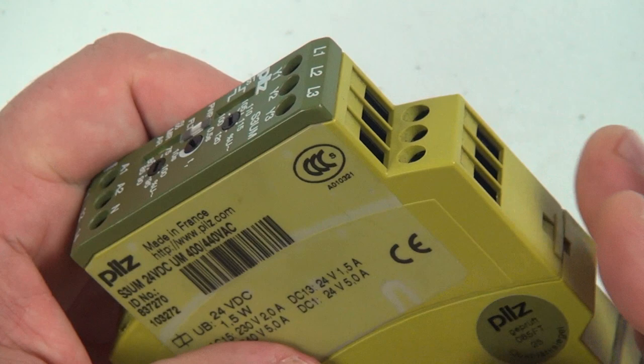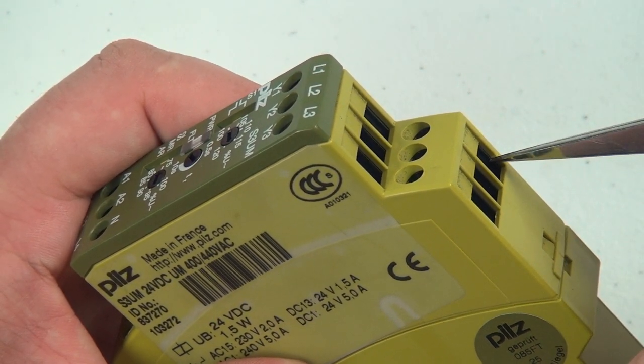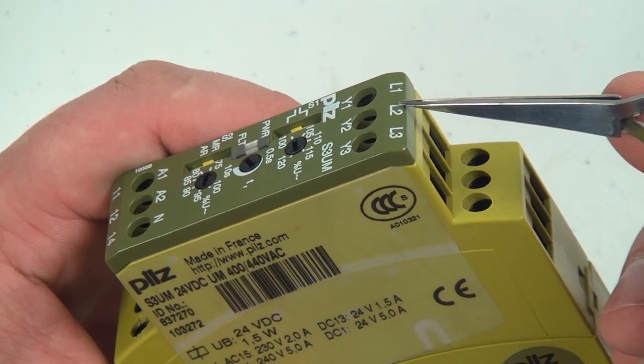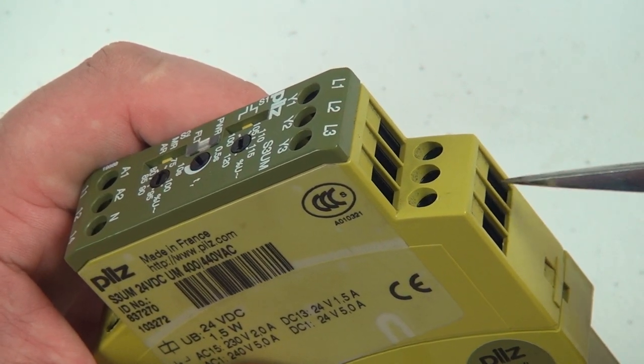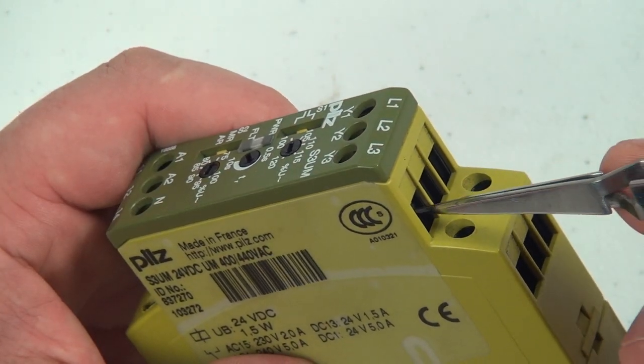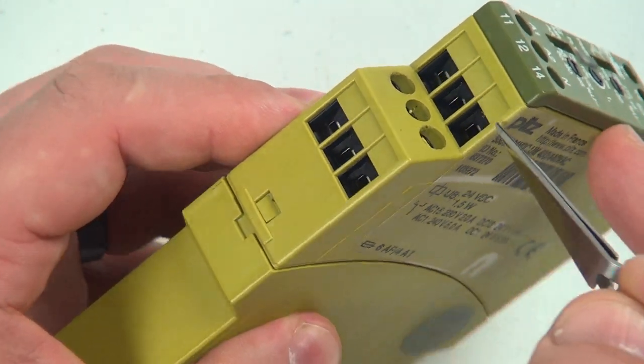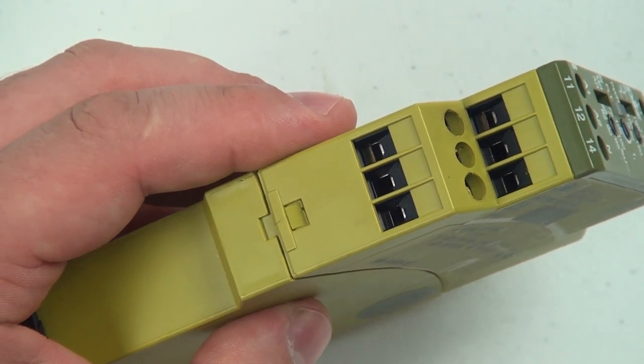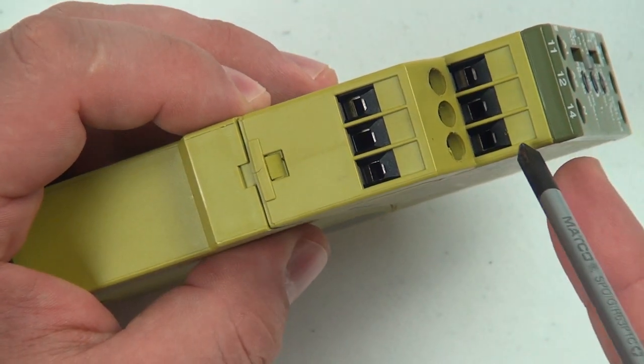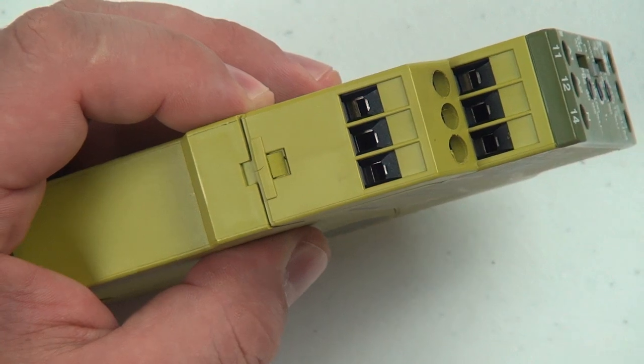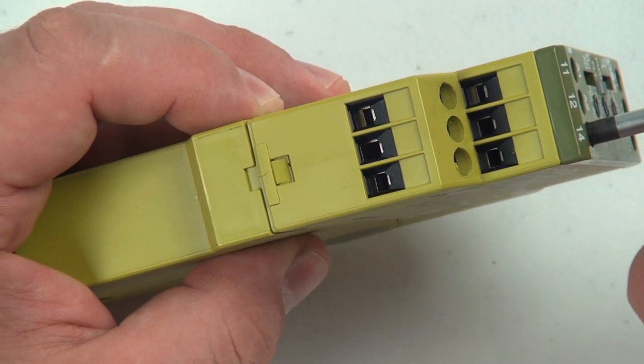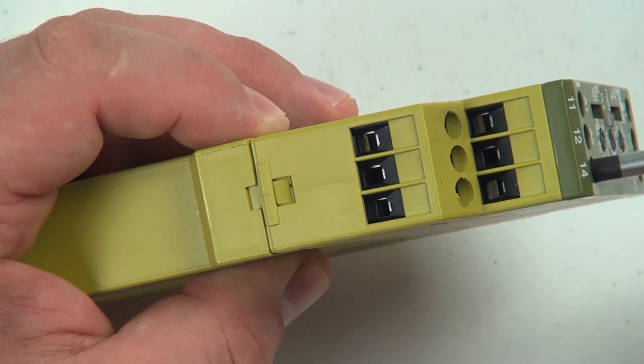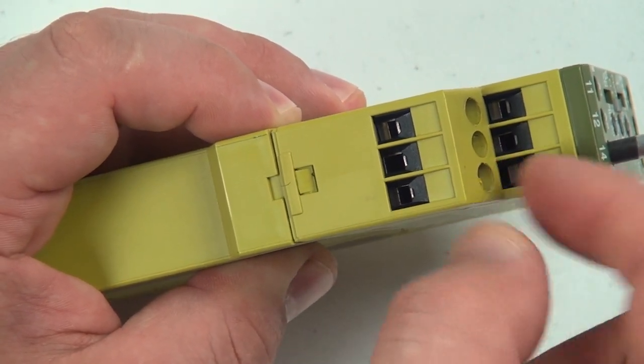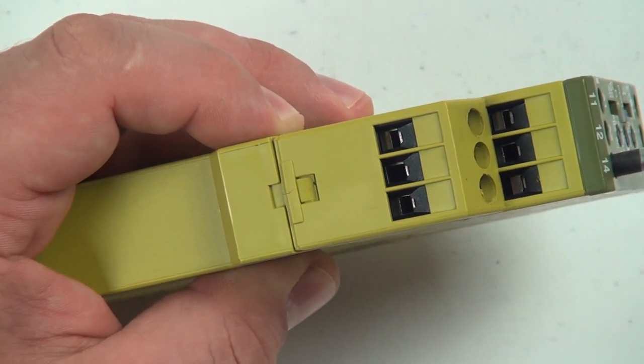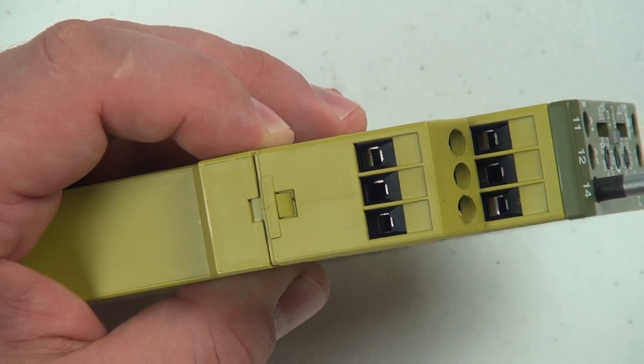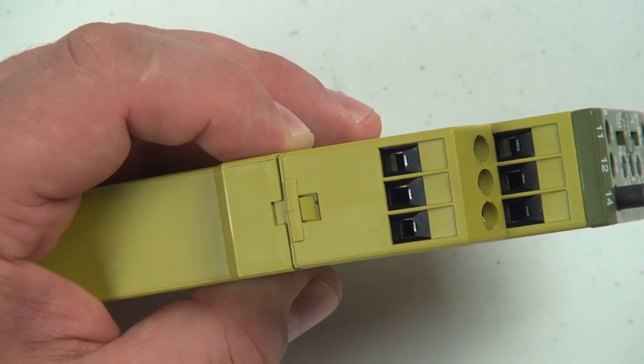And so, if we look at the relay here at an angle, you can put wires in here, and you can put wires in here. So L1, L2, L3 refer to those three lower wire holes. Y1, Y2, Y3 refer to these upper three wire holes. And those same wire holes you can see over on this side, which is probably a good point to mention because you can see them pretty well. These little clippies, I don't know what you want to call them, down here: if we put a screwdriver in here and we twist it, you can see that opening will close like that. And if you had a wire in there, now that wire would be squished on both sides by that clip. And when we want to remove the wire, we just spin the screwdriver in the opposite direction, and you can see that opening will open back up, releasing the wire.